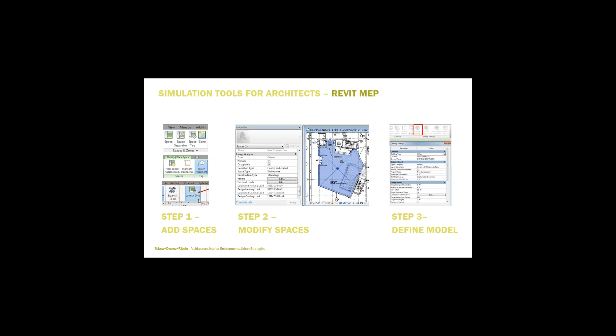This is a fairly simple workflow to report heating and cooling load calculations. We've developed schedules we're implementing in our templates and projects where you can report the name, the space type, see if it's inheriting from the building or if you're putting in something at this level. You can sit with the architect and go through these to make sure they're appropriate. This also reports outputs for cooling and heating loads, and you can look at other model inputs. It's a fantastic QA/QC and reporting tool that plugs into Revit's schedule functionality.